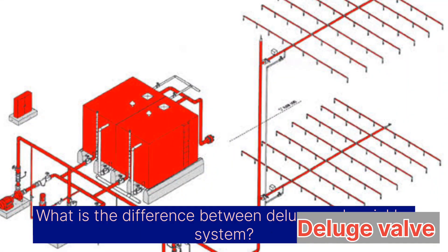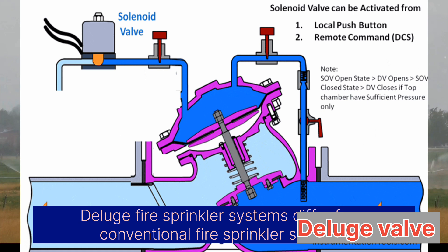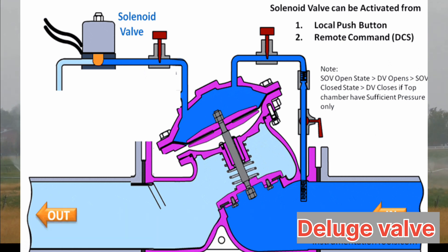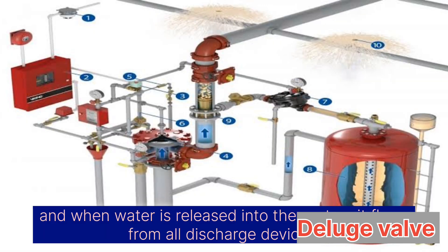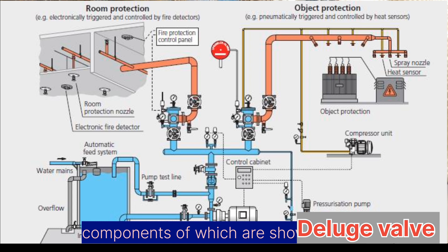What is the difference between a deluge and a sprinkler system? Deluge fire sprinkler systems differ from conventional fire sprinkler systems in the sense that all nozzles employed in the system are open, and when water is released into the system, it flows from all discharge devices. There are three main types of water deluge systems, components of which are shown below.